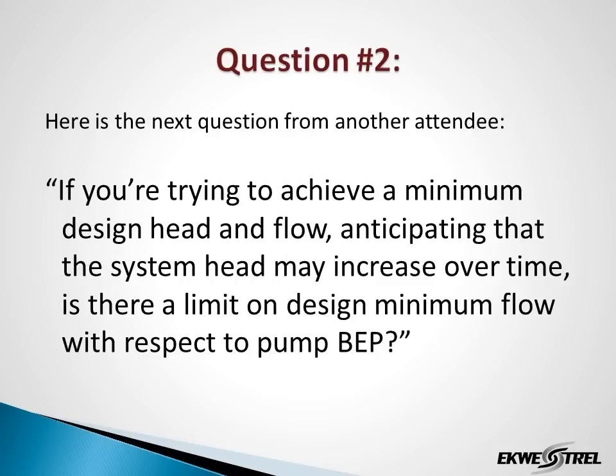Here's the next question from another attendee. If you're trying to achieve a minimum design head and flow, anticipating that the system head may increase over time, is there a limit on design minimum flow with respect to the pump BEP? It's not an absolute. The preferred lower limit of continuous operation would be around 75% or 80% of BEP, but the allowable lower limit of flow varies widely. This information might be indicated on the manufacturer performance curve.